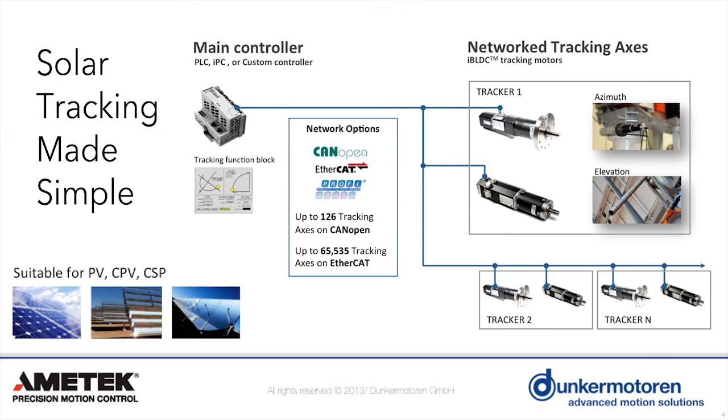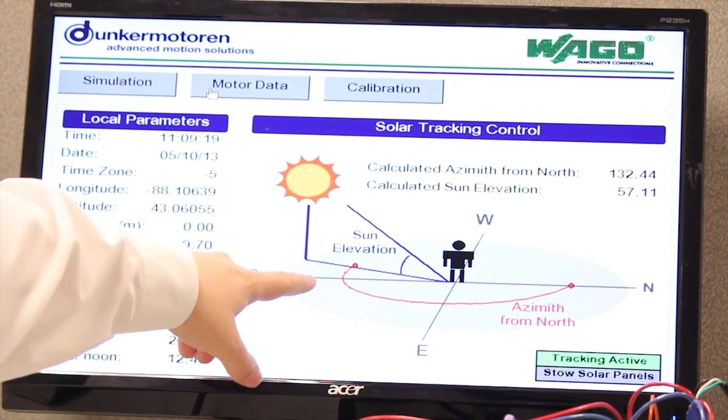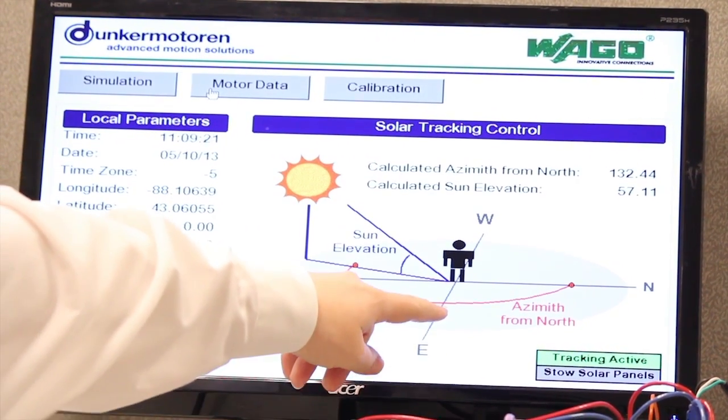In this demonstration, only two motors are connected. However, we can have up to 126 motors connected to one master. The solar tracking function block is calculating the angle of the sun in the azimuth and elevation based on the local time and GPS position.